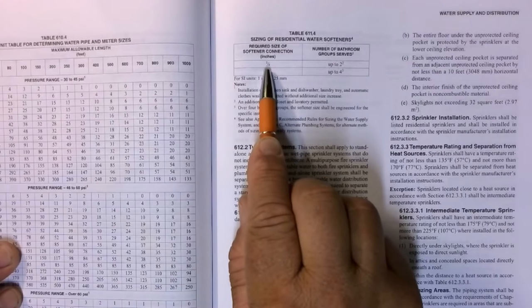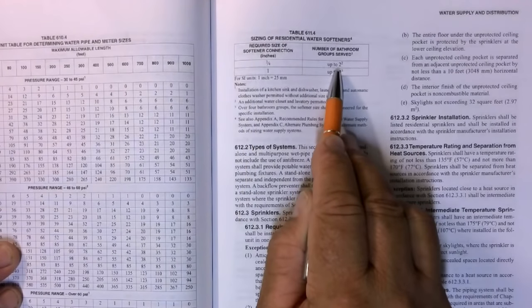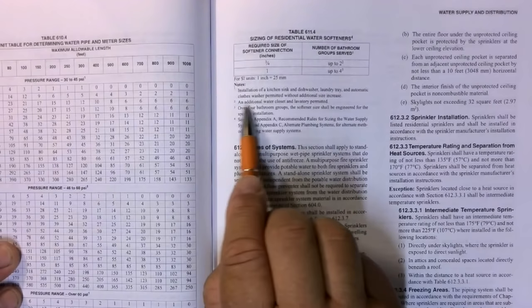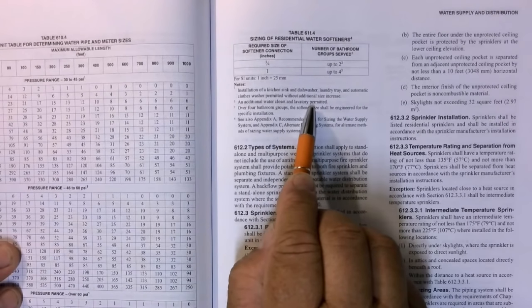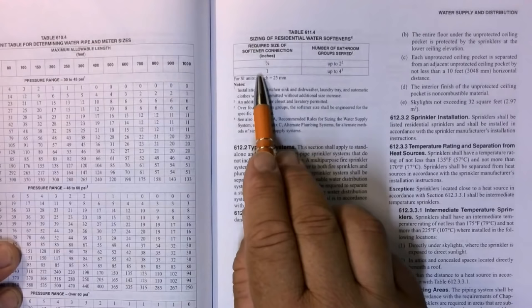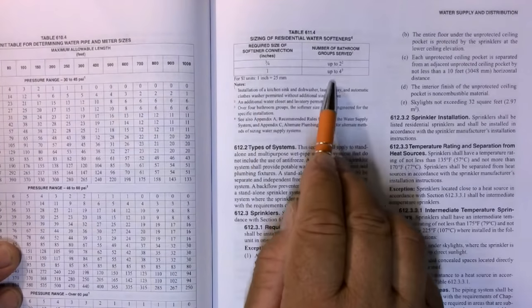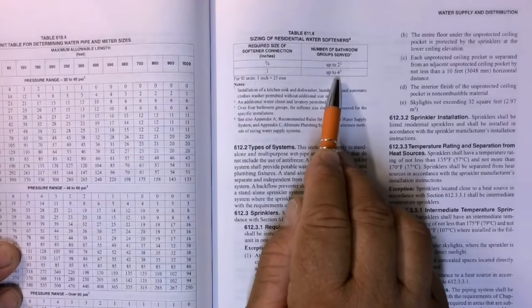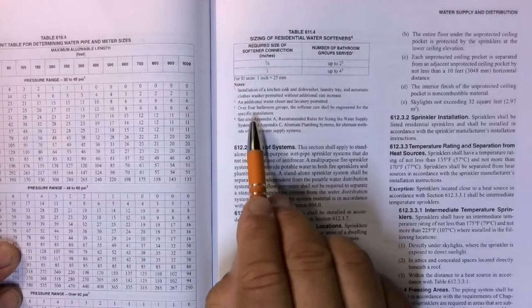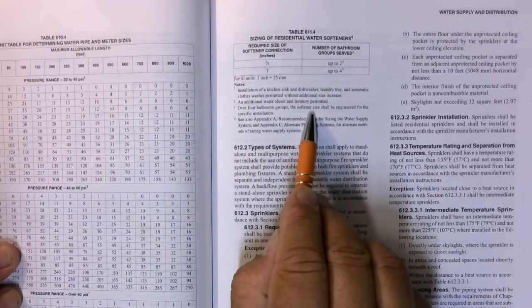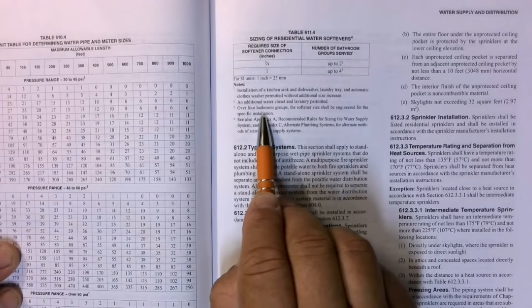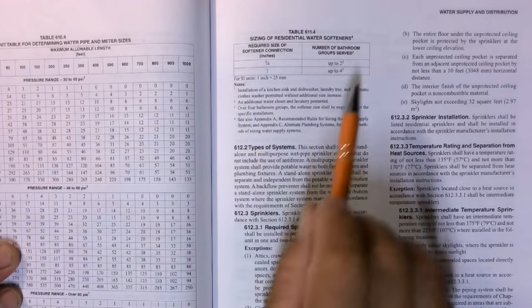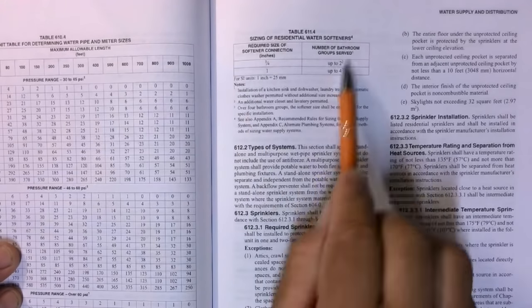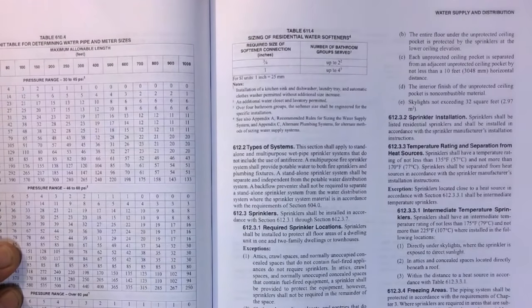So you have 3/4 size based on number of bathrooms, 2. Note 2, an additional water closet and lav is permitted. Well, that was nice of them. Required size of a softener, 1 inch. This is what it is. You got up to 4 bathrooms, okay? And then they have note 3 here, which is over 4 bathroom groups, the softener size shall be engineered for the specific installation, okay? So this is the table that you use for a residential water softener. Pretty basic, 3/4, 1 inch, you know. Anything higher than that, you got to get it engineered, and it's got to go through Appendix A.